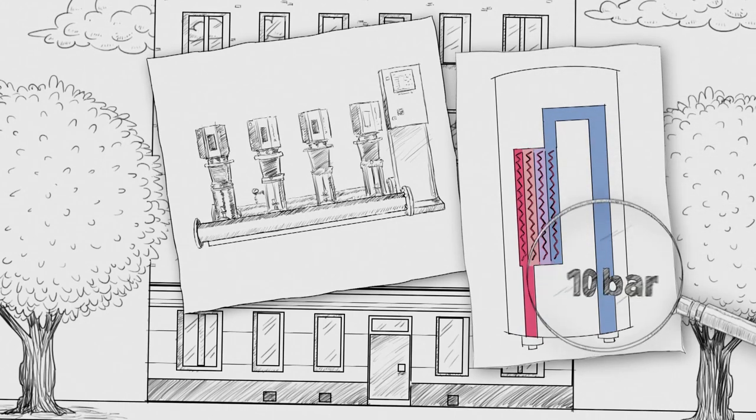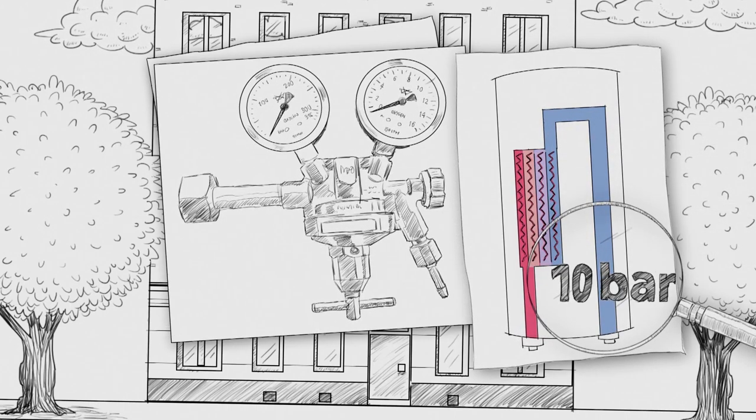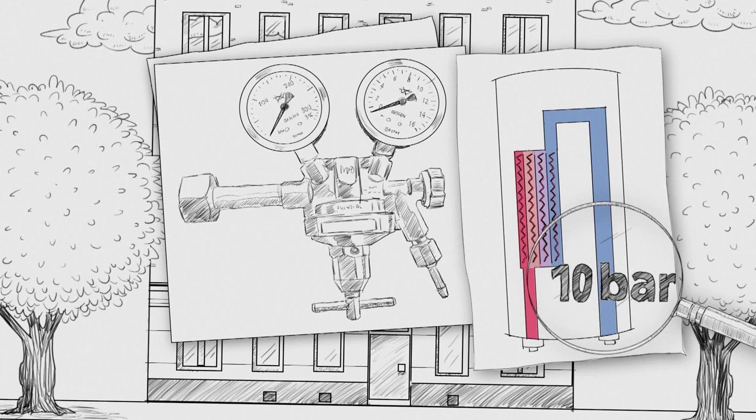Excessive mains water pressure, meaning 10 bar or higher, requires the installation of a pressure relief station to prevent damage to pipework and appliances.